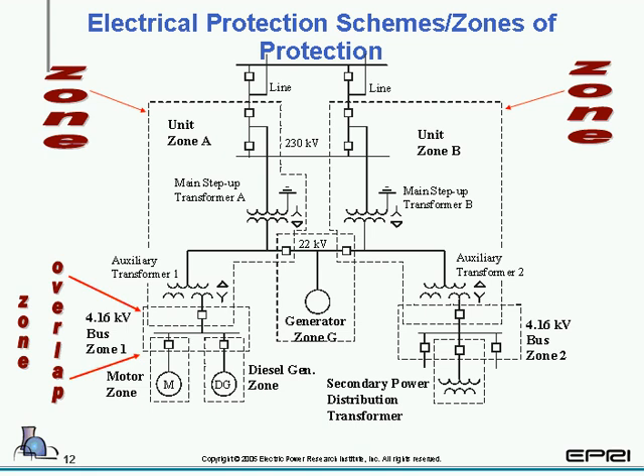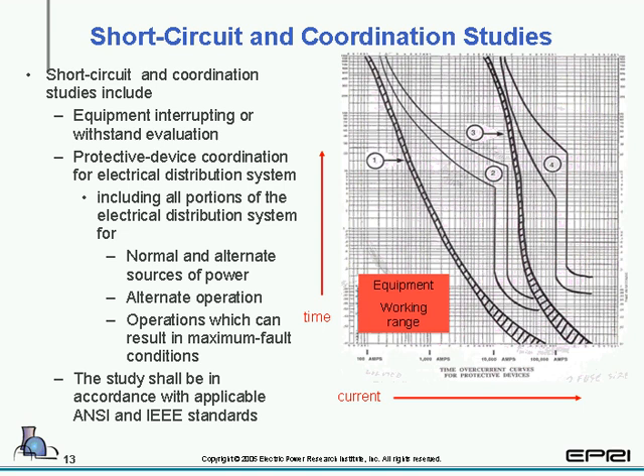After the electrical protection scheme is set up, you're going to take a look at short circuit and coordination studies. The short circuit and coordination studies deal with the equipment interrupting or withstand evaluation of the particular equipment. You're going to see down in the left-hand box we actually have the equipment in its working range. The protective device coordination for electrical distribution systems includes all portions of the electrical distribution systems, and we have a list of the basic ones. And all studies shall be in accordance with applicable ANSI and IEEE standards. Now, when we look at this particular equipment, it's going to be in its working range.